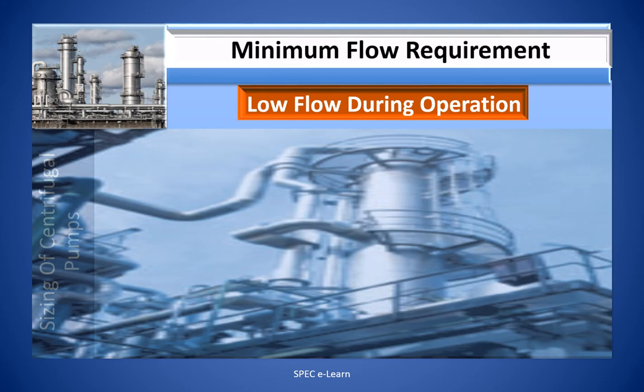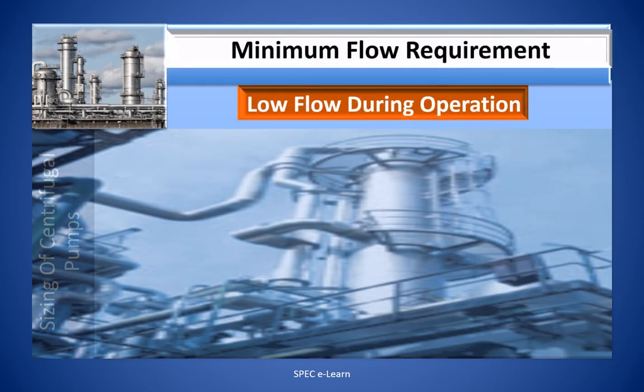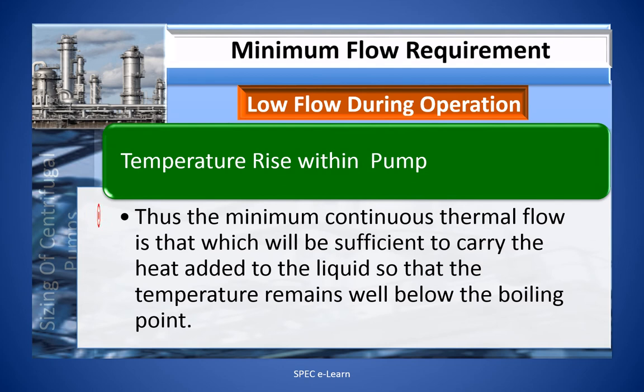Temperature rise within a pump is an important parameter when determining the minimum flow requirement. When operated away from its best efficiency point flow, inefficient operation results in heat being added to the fluid as it travels through the pump. At extremely low flow, the heat added can raise the temperature to the boiling point of the liquid at the suction pressure, resulting in vapor pocket formation within the pump — causing vapor lock and unstable operation.